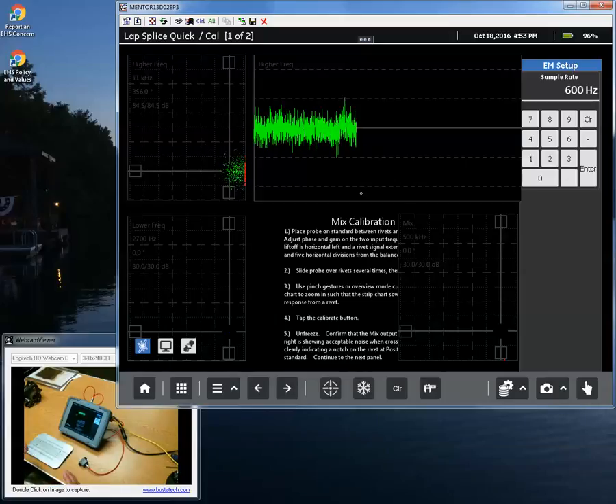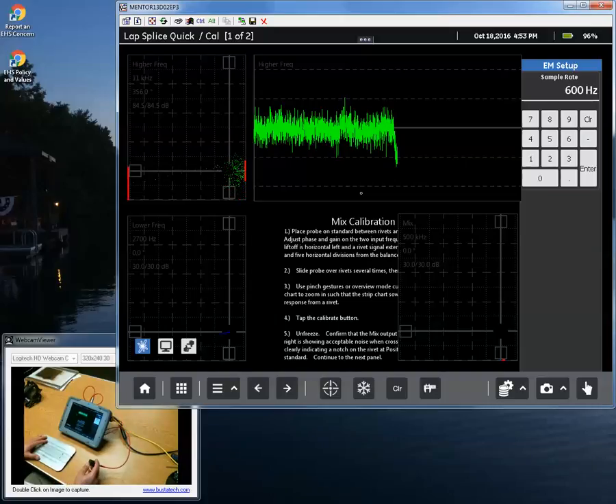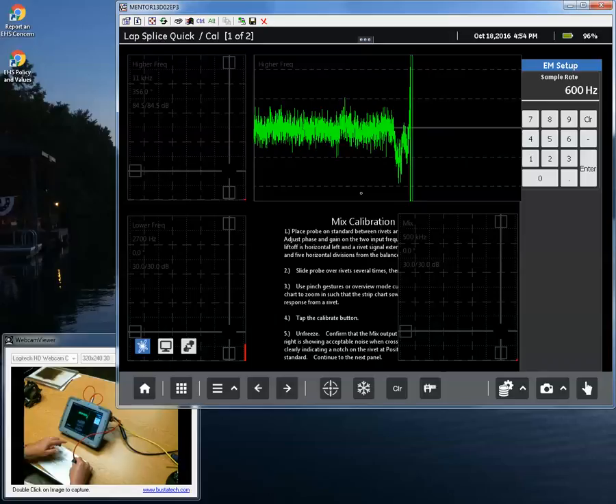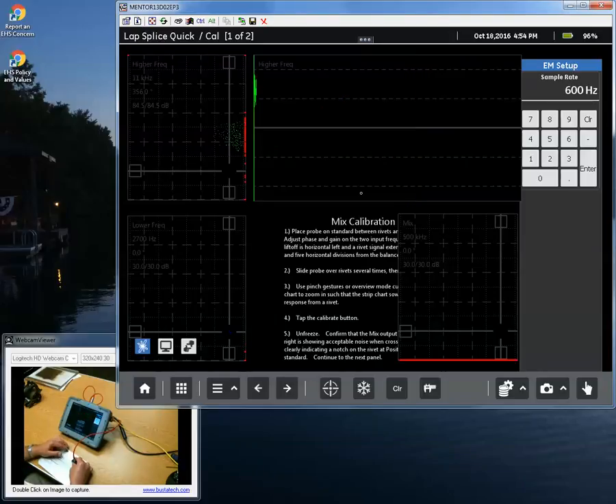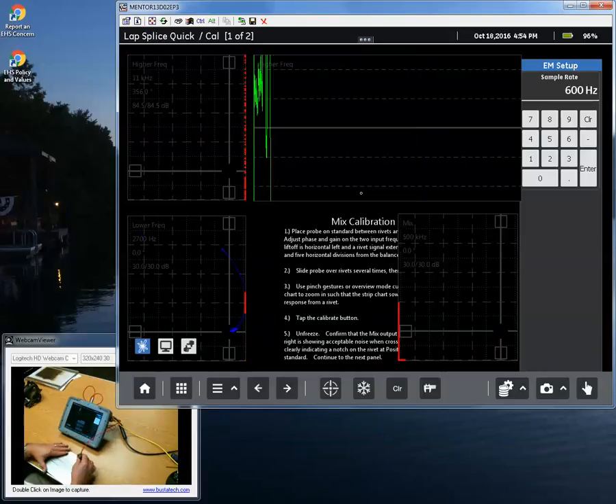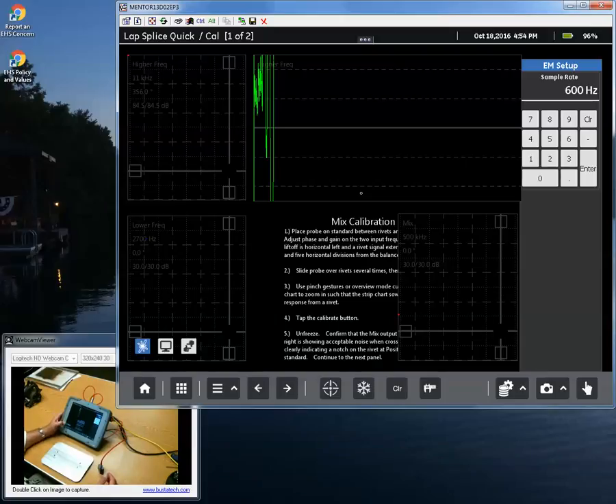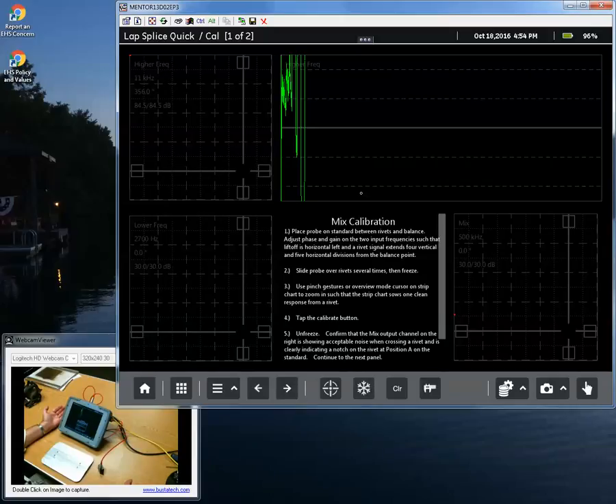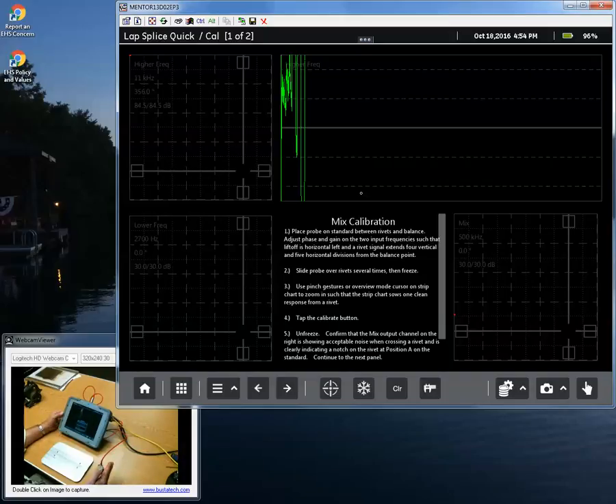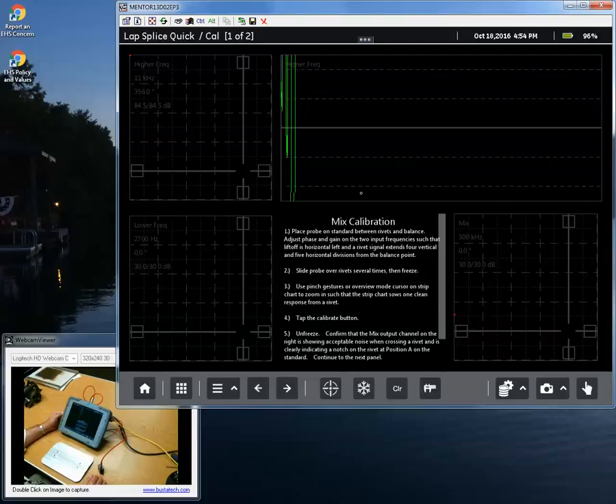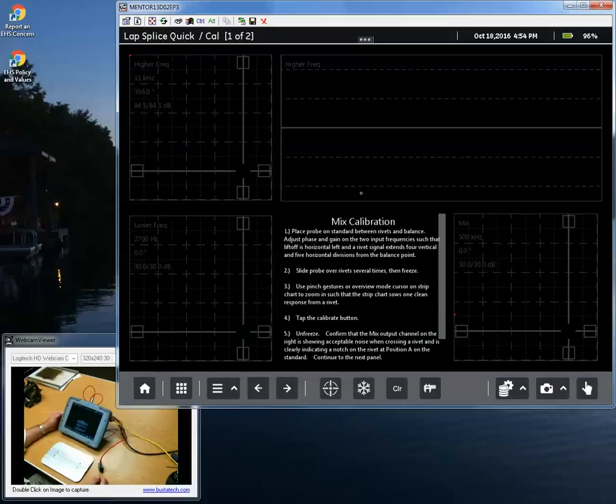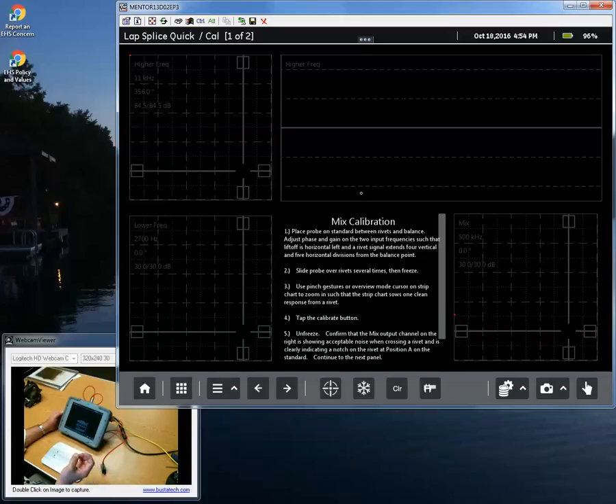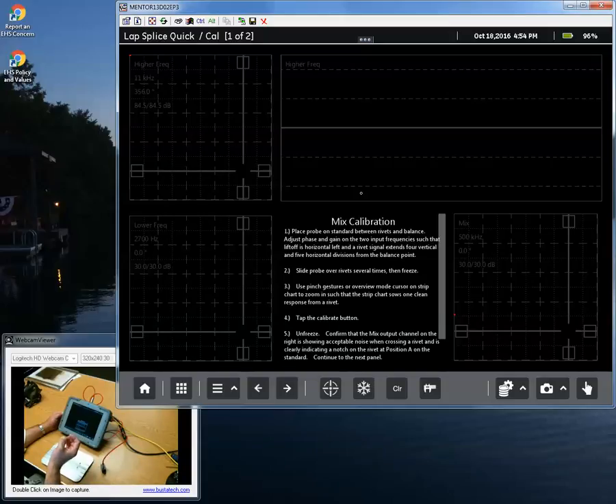However, the slower the sample rate, the lower the sample rate, the slower the probe has to be passed over the part, over the defect, in order to see the defect. In high speed applications, say you're using a differential probe on steel, typically you might use a 100 kilohertz frequency. Very commonly you would use a 1 kilohertz sample rate, so you're able to demodulate on 100 cycles of the carrier wave. It gives you an excellent signal-to-noise ratio. If you had a very high speed test, say drawn wire moving at several inches per second past the probe...